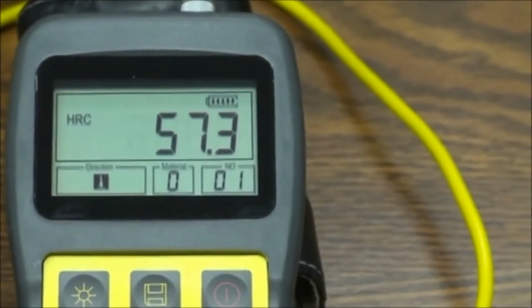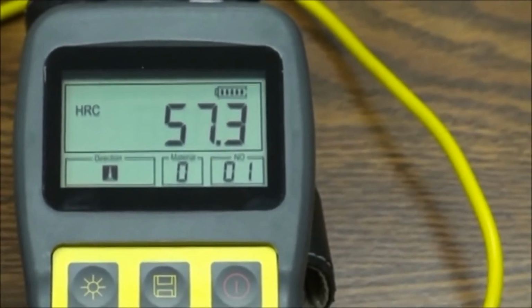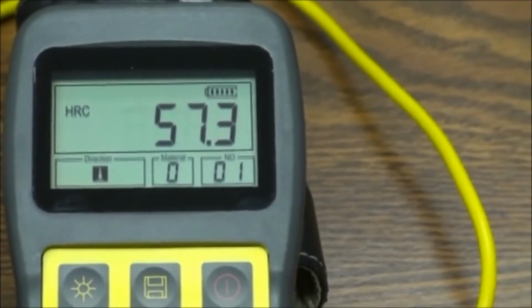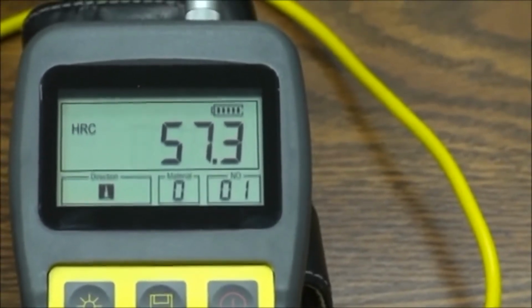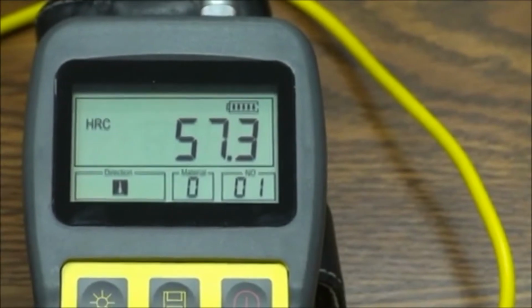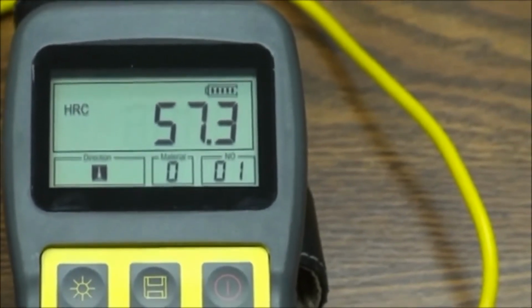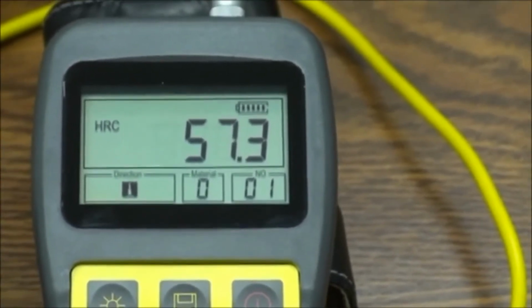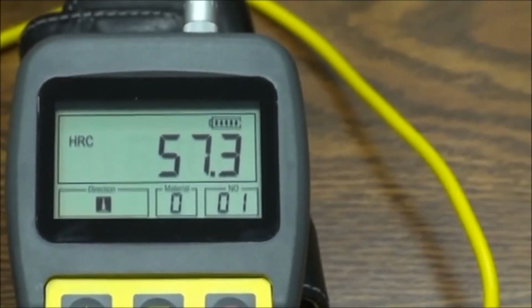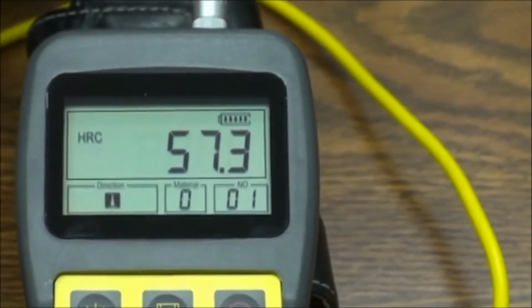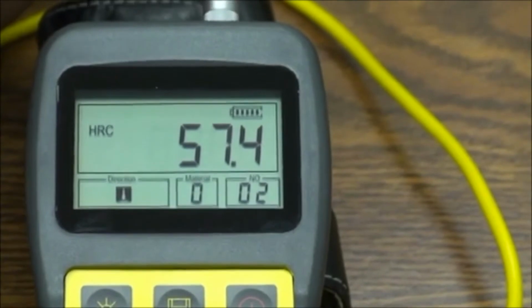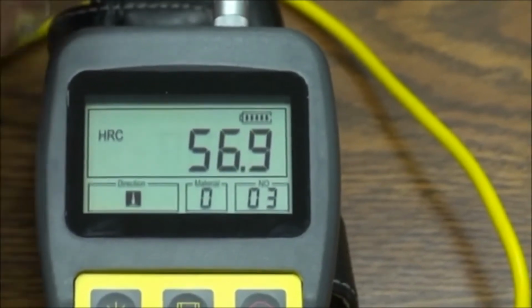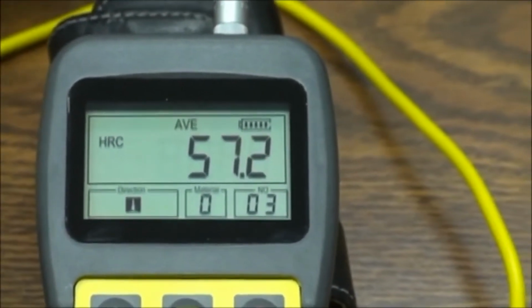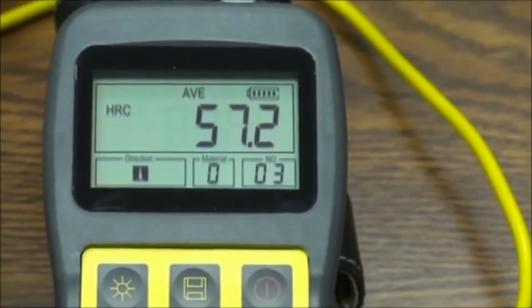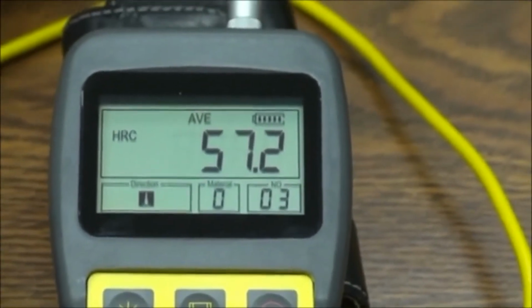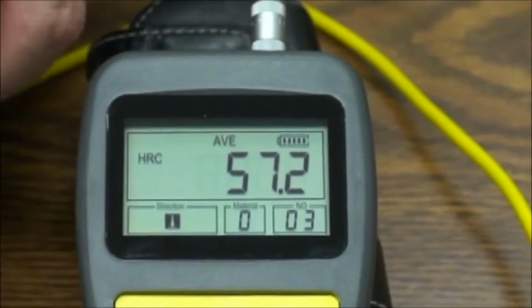direction of probe during test, the material selected, the scale you are reading in, and the number of tests you have taken. The number will revert back to 0 once you have reached the number of tests to take an average. At that time, then an average will show on the screen. Taking a series of quick burst tests are rather simple and easy.